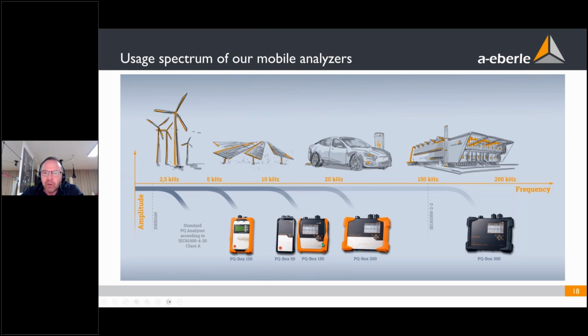The PQ-Box 150 and 50, here the sampling frequency is 20 kilohertz. So we can measure all of the disturbances in our grid up to 10 kilohertz. The PQ-Box 200 has a sampling of 41 kilohertz. We can measure up to 20. And the high-end box, the PQ-Box 300, has a sampling frequency of 409 kilohertz, and we can measure online up to 200 kilohertz and offline permanent up to 170 kilohertz. But 150 is a must because the standard provides limits up to 150 kilohertz.